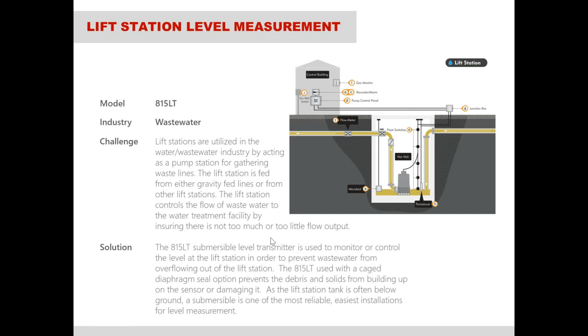So, submersible pressure transmitter applications. One of the big ones is lift stations for water wastewater treatment facilities. Sewage systems and sewer lines from houses and businesses and residential areas all have to be pumped to a water wastewater treatment facility, and they'll have what are called lift stations. These are basically booster stations. If the origin of the waste is far away from the wastewater treatment facility, then you need these little booster stations, or lift stations, to push it along to the station.